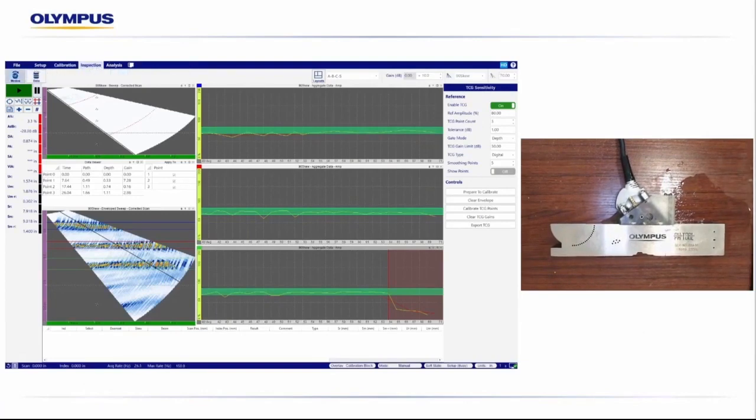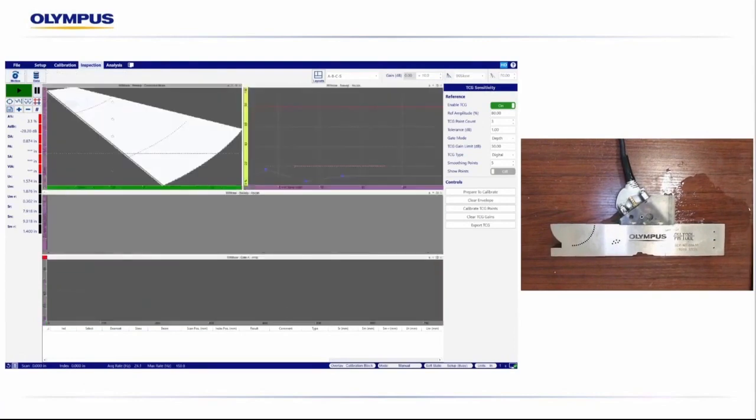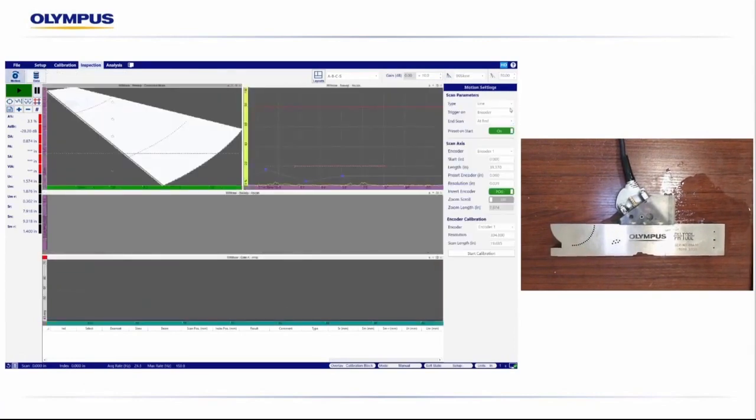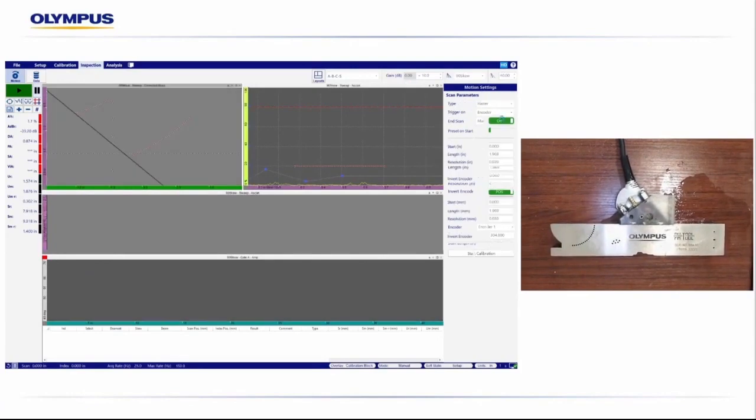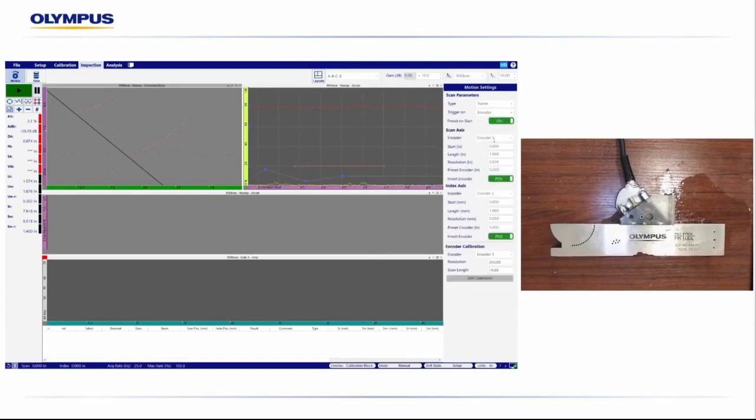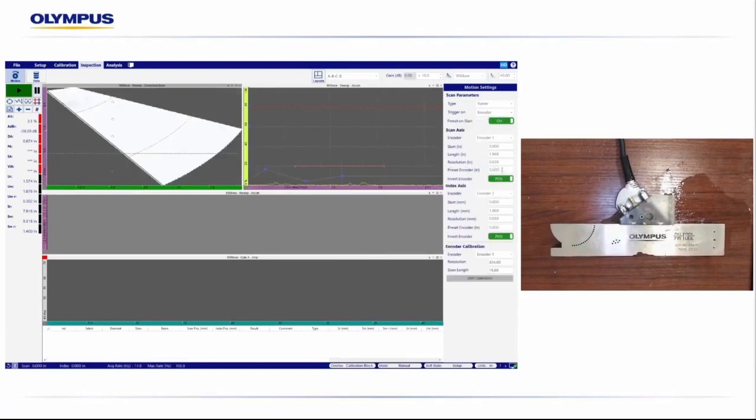Once we're happy with our calibrations, we're only going to run a single probe in this specific demonstration. We can also even export the TCGs, copy them to the other group, or copy the whole calibration from one probe to the other. Let's slide over to the Inspection tab. In our Motion settings here, we'll specify our scan type, whether we're doing just a single line scan, running down the length of the weld, or doing a full raster scan. Input all of our encoder parameters, our scan parameters, and we are ready to start our inspection.